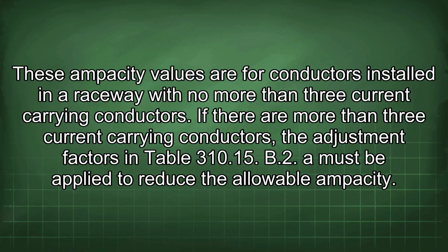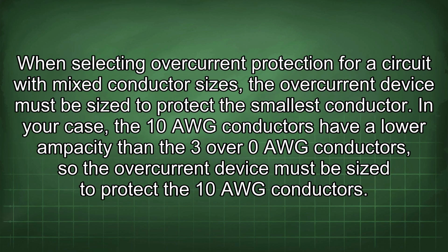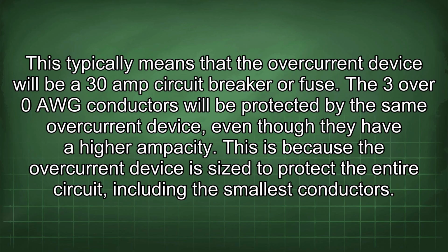These ampacity values are for conductors installed in a raceway with no more than 3 current-carrying conductors. If there are more than 3 current-carrying conductors, the adjustment factors in table 310.15 B 2 must be applied to reduce the allowable ampacity. When selecting overcurrent protection for a circuit with mixed conductor sizes, the overcurrent device must be sized to protect the smallest conductor. In your case, the 10 AWG conductors have a lower ampacity than the 3/0 AWG conductors, so the overcurrent device must be sized to protect the 10 AWG conductors. This typically means that the overcurrent device will be a 30 amp circuit breaker or fuse. The 3/0 AWG conductors will be protected by the same overcurrent device, even though they have a higher ampacity. This is because the overcurrent device is sized to protect the entire circuit, including the smallest conductors.